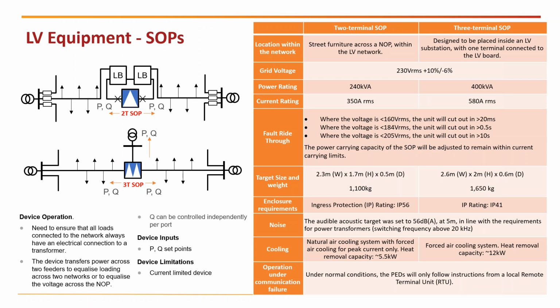so it can be hosted in a secondary substation or an LV-only substation. In terms of power rating, we're talking about 240 kVA for the 2-terminal and 400 kVA for the 3-terminal SOP. Just to give you a bit of reference, the transformers that we have in a secondary substation are between 500 kVA and 1000, so quite substantial support that we can have from these devices. And one of the most important things is the fact that we are going to use silicon carbide. Silicon carbide is the key material that Turbo Power Systems are using to create this excellent device. It is a good challenge, very interesting, to use a different material, but the benefits they are delivering are quite incredible.